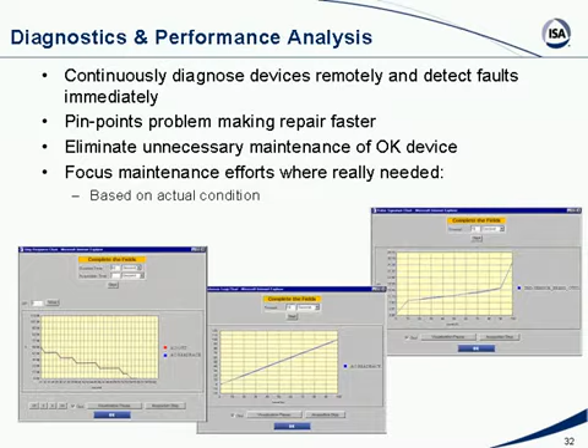Operational statistics allow me to predict failure. I can estimate remaining service life. This is how it works. The valve manufacturer may tell me that I need to replace the stem packing every 100,000 reversals. So I key in a limit of 90,000 in my positioner. After 90,000 reversals, the positioner tells me it's time to get the spare parts and schedule maintenance. So then I can fix this stem packing before it fails, and I don't do it unnecessarily early.